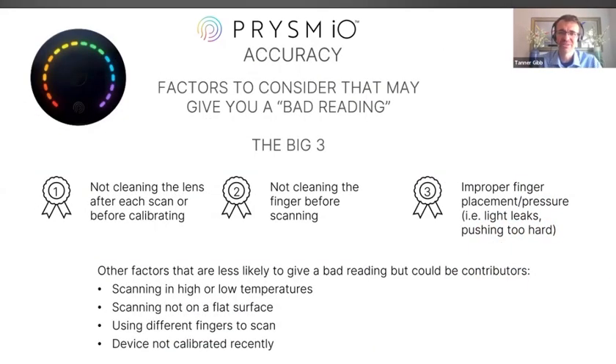If I could summarize these into the big three, what are the big three that are going to create a bad reading? Number one, you're not cleaning the lens after each scan or before calibrating. Number two, you're not cleaning the finger before scanning. And number three, improper finger placement or pressure that can lead to light leaks or pushing too hard. Yes, there are other variables at play, right? Scanning at higher or lower temperatures, not on a flat surface, using different fingers, a device not calibrated recently, etc.